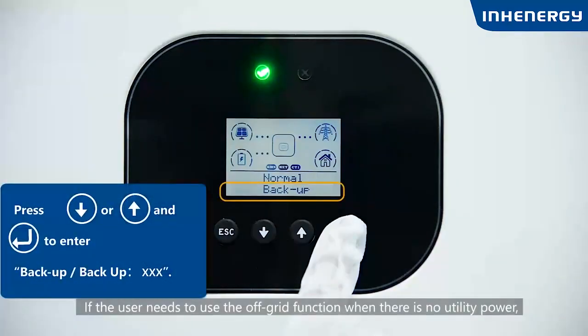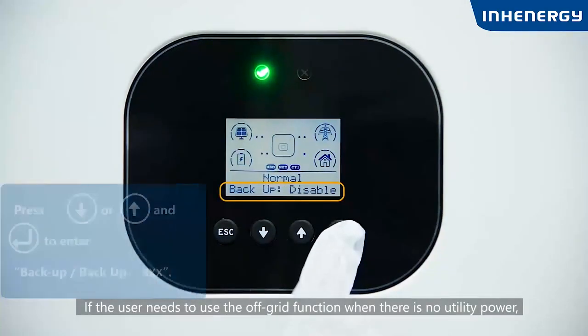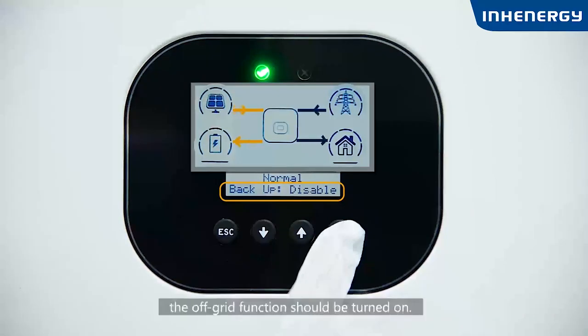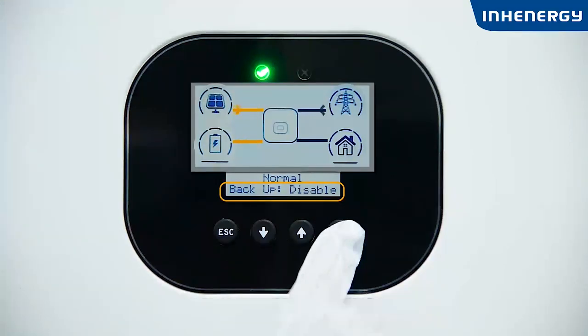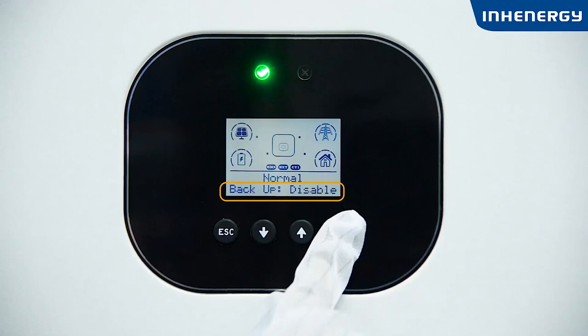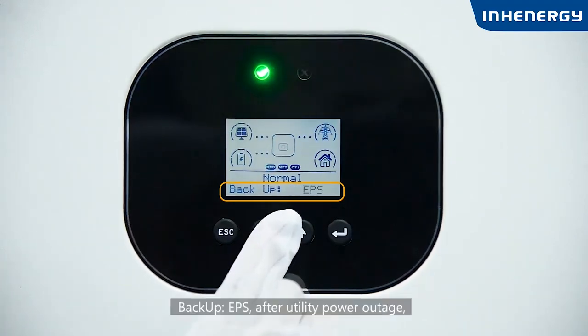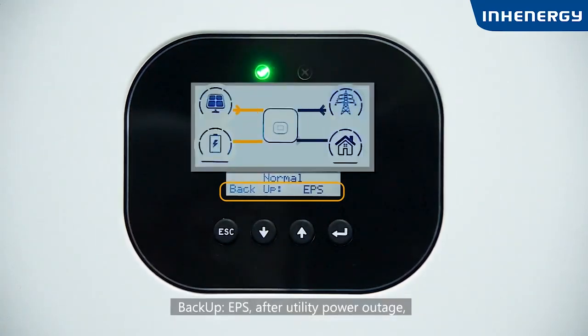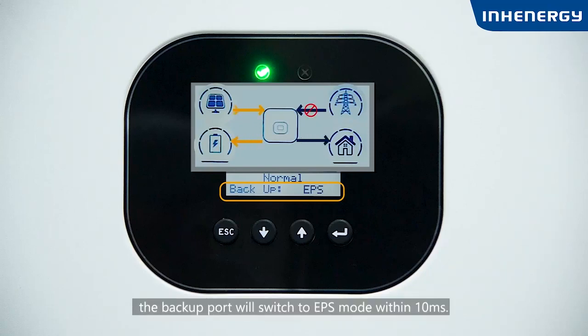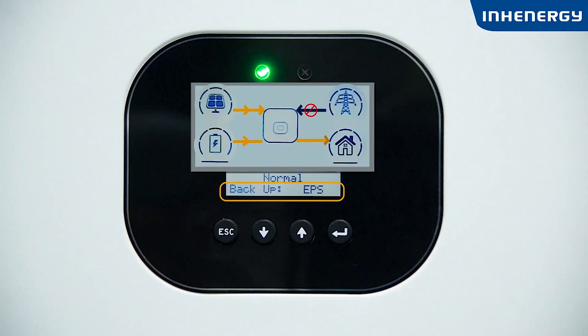If the user needs to use the off-grid function when there is no utility power, the off-grid function should be turned on. Backup EPS: after utility power outage, the backup port will switch to EPS mode within 10 milliseconds.